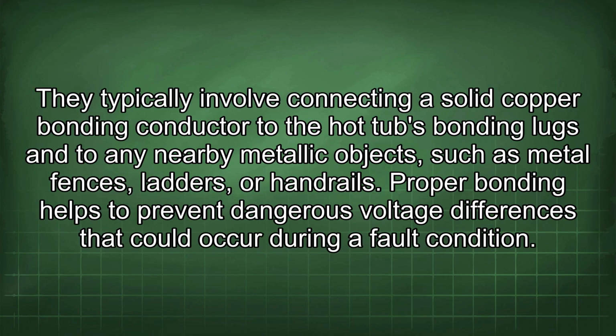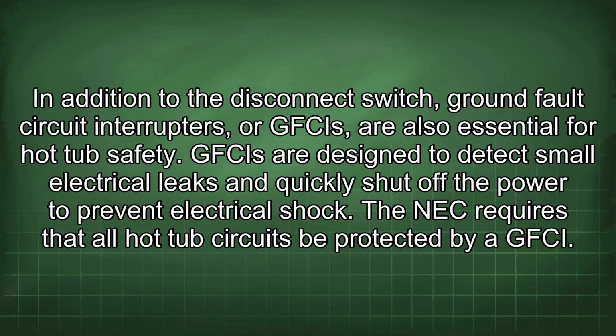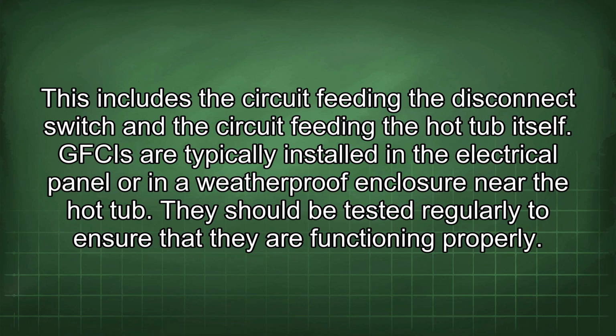They typically involve connecting a solid copper bonding conductor to the hot tub's bonding lugs and to any nearby metallic objects, such as metal fences, ladders, or handrails. Proper bonding helps to prevent dangerous voltage differences that could occur during a fault condition. In addition to the disconnect switch, ground fault circuit interrupters, or GFCIs, are also essential for hot tub safety. GFCIs are designed to detect small electrical leaks and quickly shut off the power to prevent electrical shock. The NEC requires that all hot tub circuits be protected by a GFCI. This includes the circuit feeding the disconnect switch and the circuit feeding the hot tub itself.